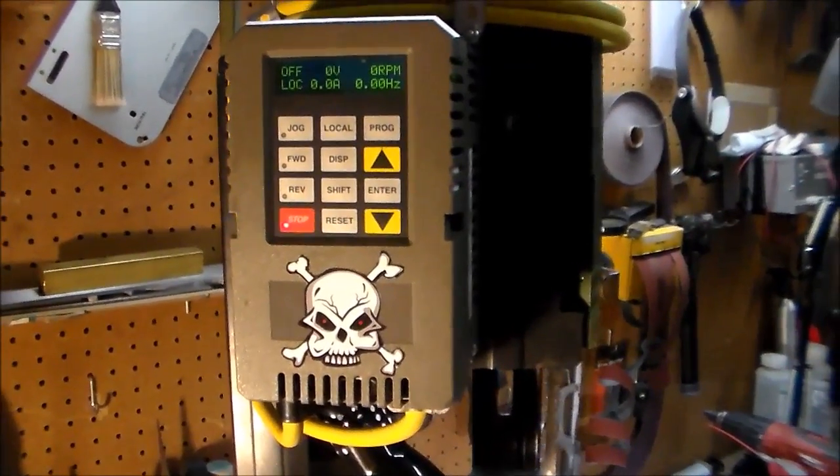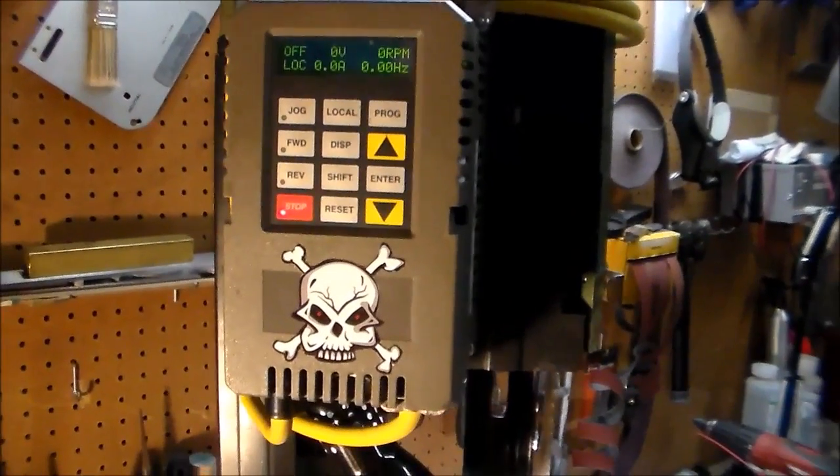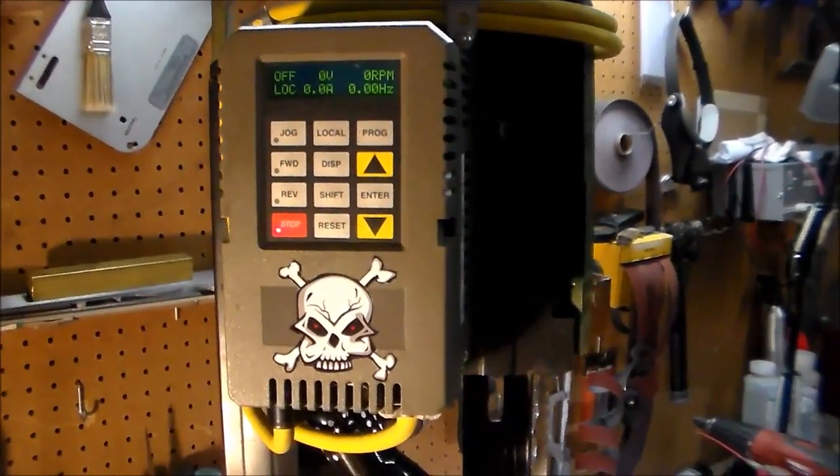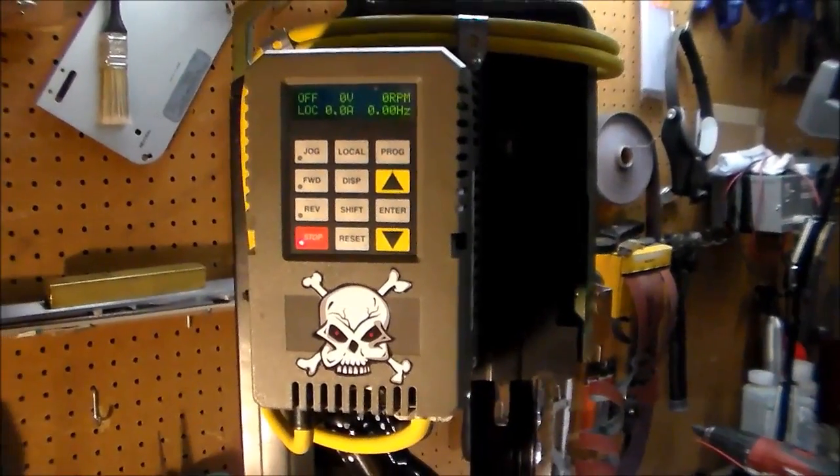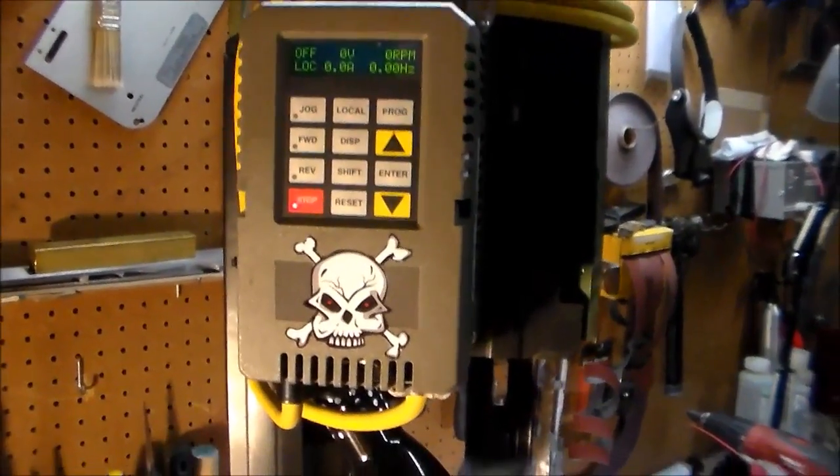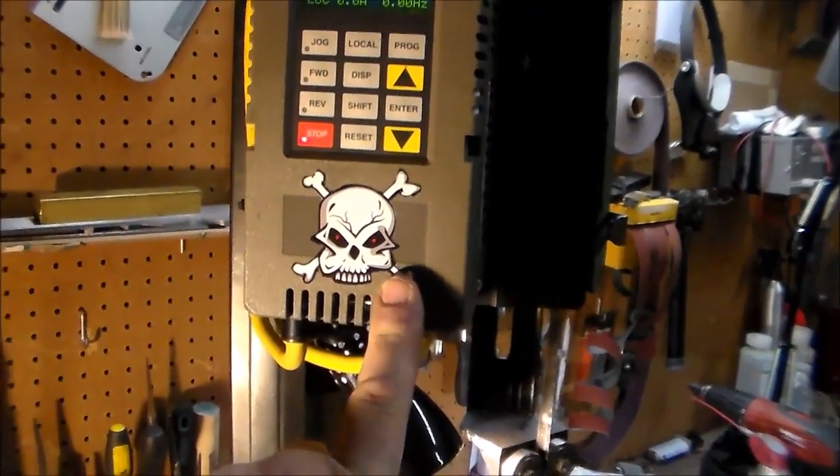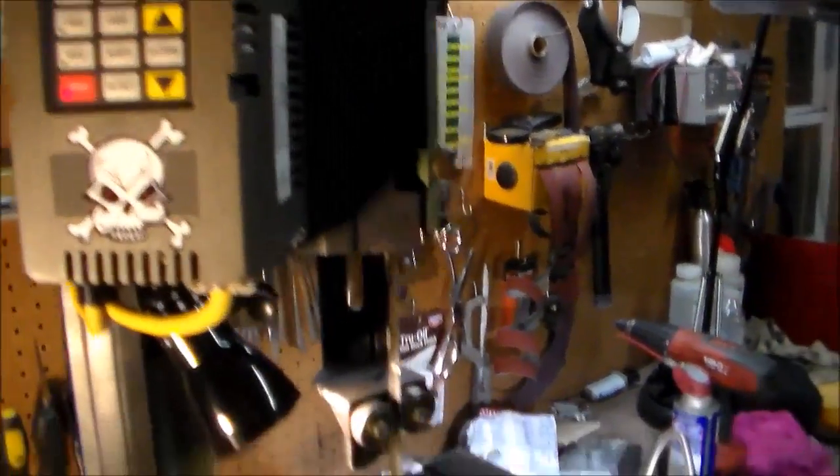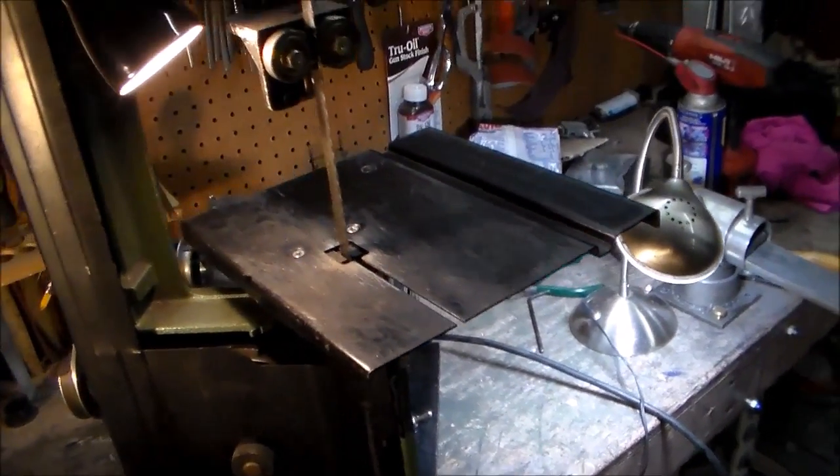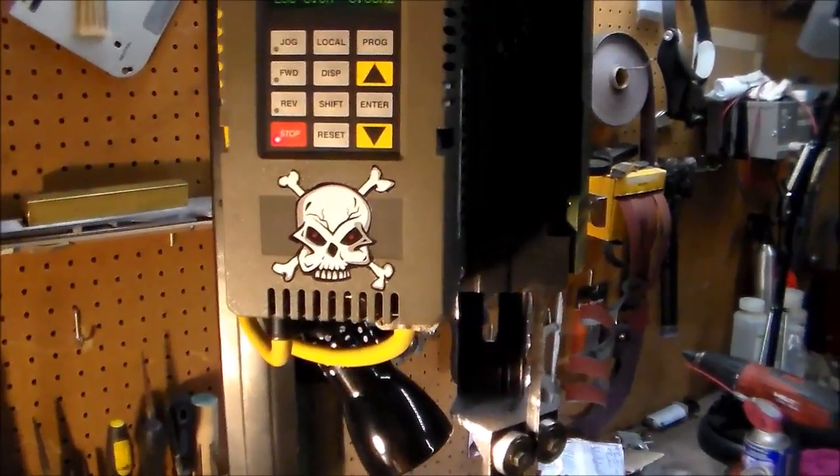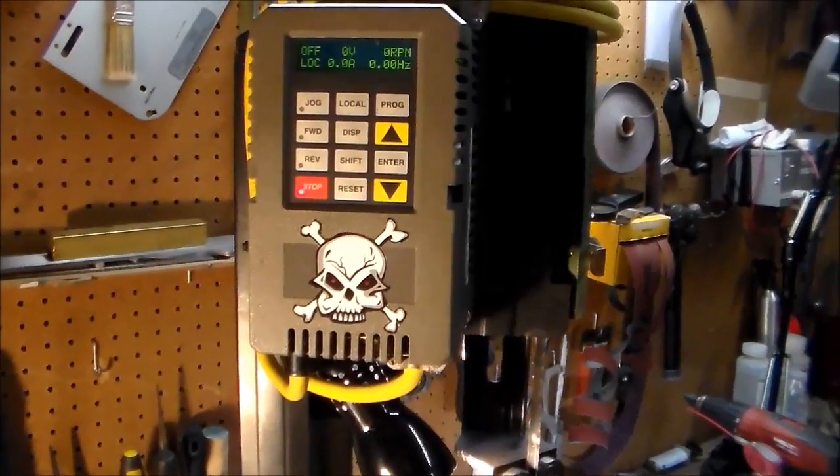If you have to have your motor go a certain way when you press the forward button. And the first time you turn it on, it goes the other way. It's simple. You either rotate two of the wires on this end of the motor lead or two of the wires on that end. You just pick whichever ends easiest to get to for you. But you know, not both. Just one end. You roll two of those wires and it'll change the direction of the motor.